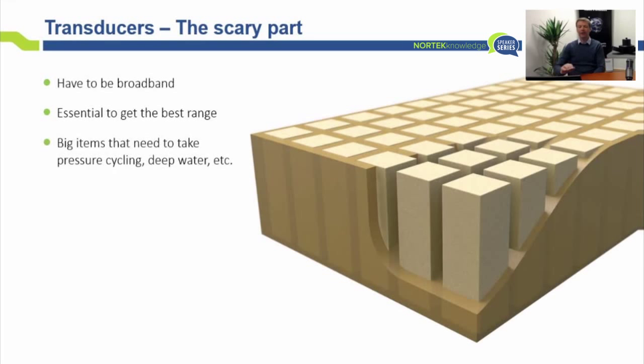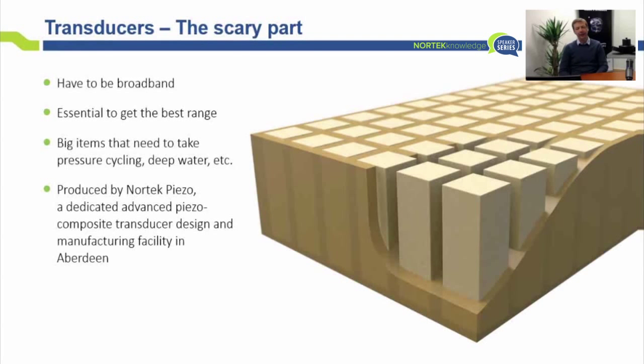And we were lucky enough that we were able to take advantage of the acquisition of a small company in Aberdeen, which was called PCT at the time, and then later on became Nortek Piezo, which is basically a dedicated production facility that makes piezo composite transducers. And this allows us to take smaller blocks of transducers or transducer elements and put them together into larger disks. It also allows us to remove a lot of the material that's being used in the ceramic, so that even if it is very large, it's still quite light compared to what a solid ceramic is, because you're removing a significant portion of the material in the process of making these things. So you get the broadband and you get lighter transducers sort of almost for free.